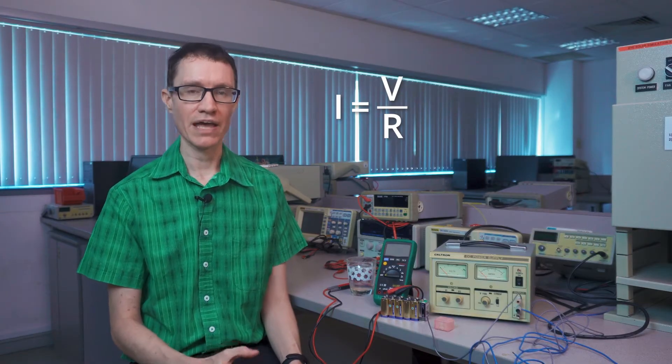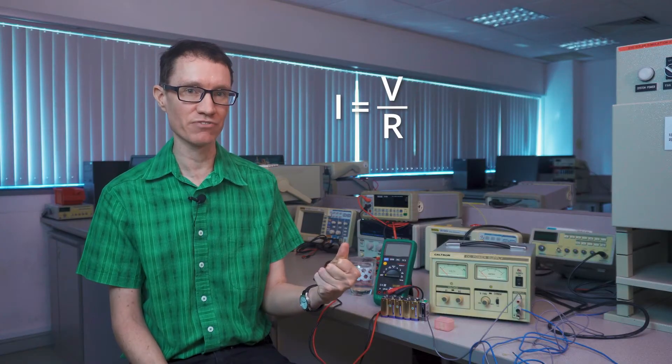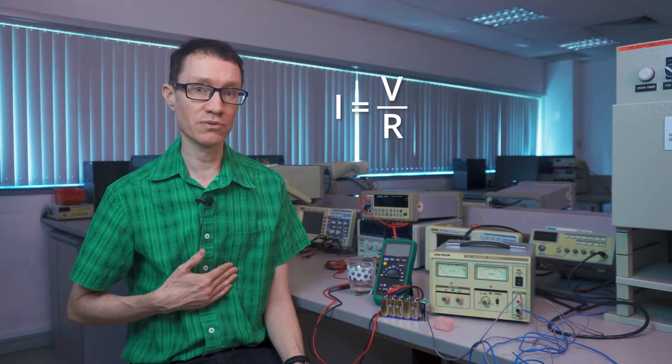At the one milliamp level, you would be able to feel the current. At the 10 milliamp level, your muscles would contract and you might not be able to let go of a conductor if you were getting shocked. At the 50 milliamp level, it's likely that the human heart would fibrillate and that would probably prove fatal.